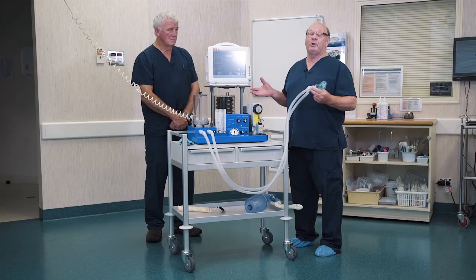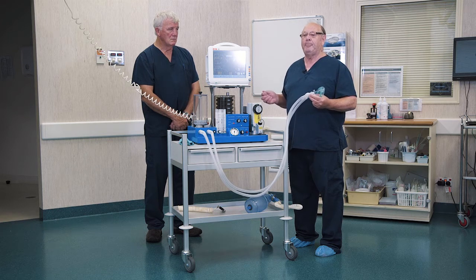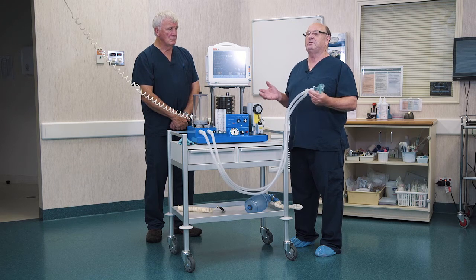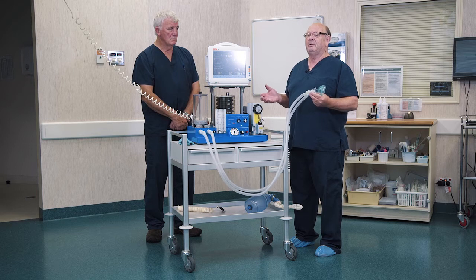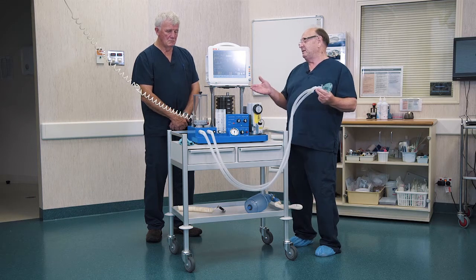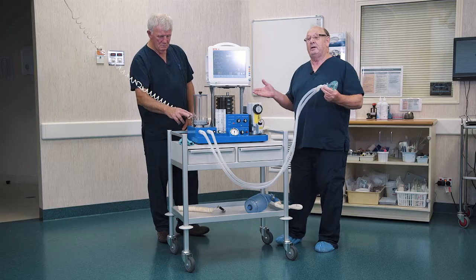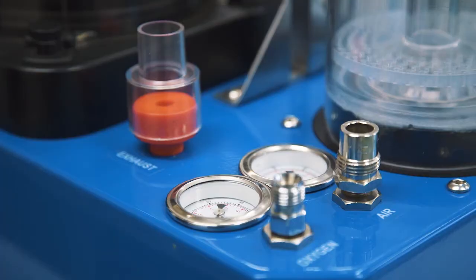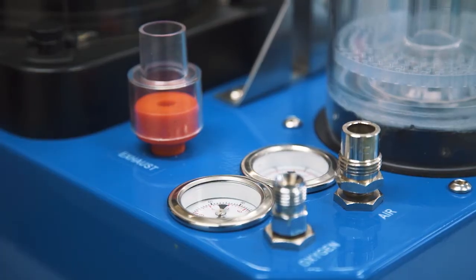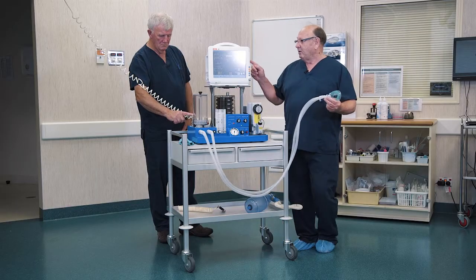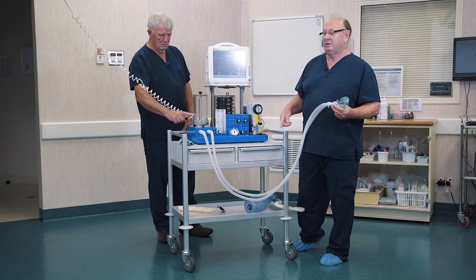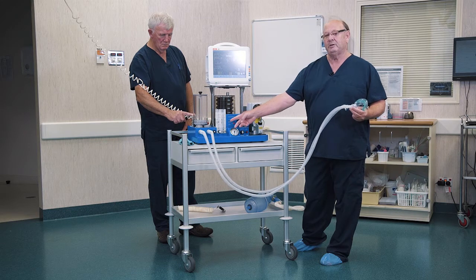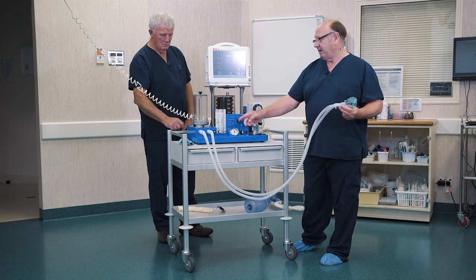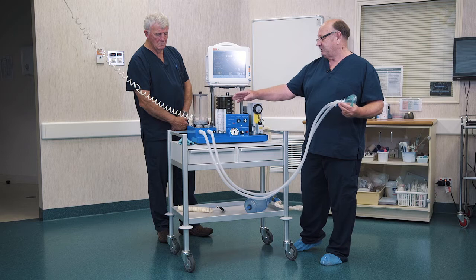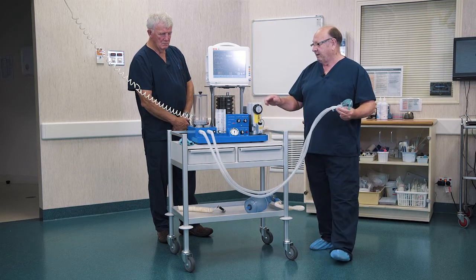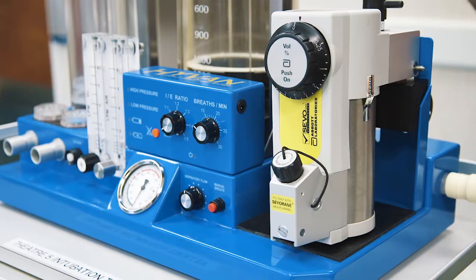It works pretty much the same as any anaesthetic machine, but there are a few differences in this machine which I'll explain to you. Firstly, the gases, just like normal gases, enter the rear of the machine at 2 pin-indexed entry ports. From there, the oxygen comes through tubes down to these 2 flow meters, 1 oxygen and 1 air. They are mixed together and then they flow again into the Selectatec type vaporizer.